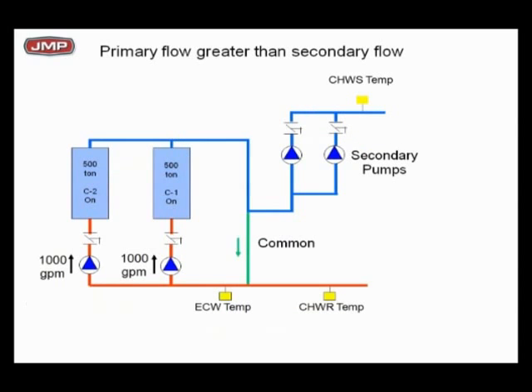So let's keep going with this concept, and let's go with the primary flow rate greater than the secondary. I've got two chillers online now, chiller 1 and chiller 2, so I'm producing 2,000 GPM of 44 degree water. Both chillers running, 2 GPM per ton, 1,000 tons there, I can produce, and I am producing, 2,000 GPM of 44 degree water. Now, how much water are we going to take out in the secondary loop? Well, let's take out 1,500 GPM. So now we get more to a real world situation. I've taken 1,500 out. What does that mean to my common pipe?